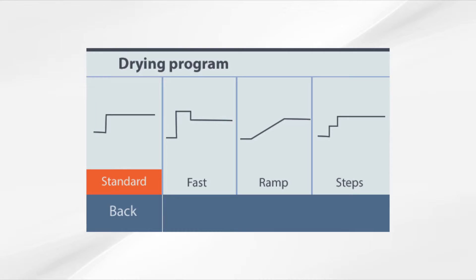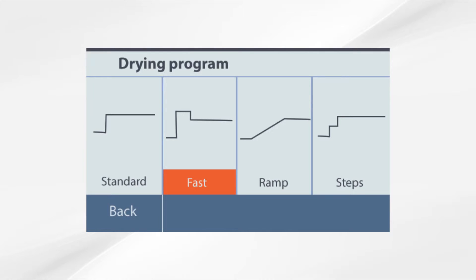The Standard Drying Profile is the most commonly used setting. The moisture balance will heat up to the target temperature and hold throughout the test. The Fast Drying Profile is ideal for samples with high moisture content. The target temperature is exceeded by 40% for the first three minutes, then reverts to the target temperature, which is sustained until the end of the measurement.